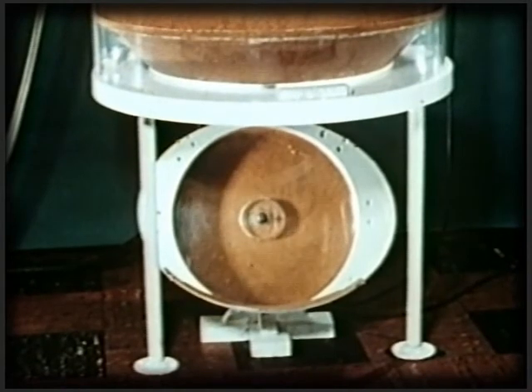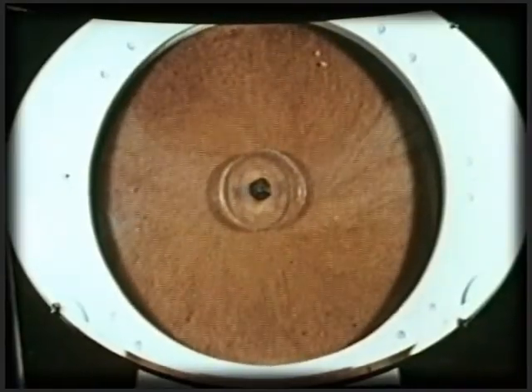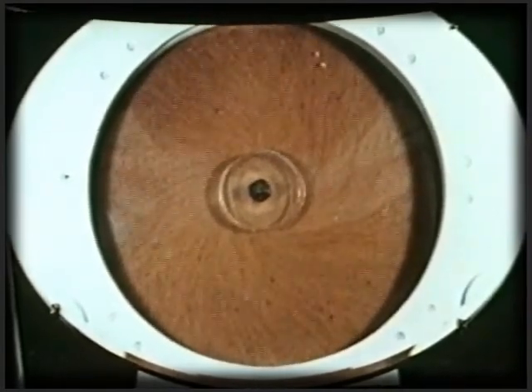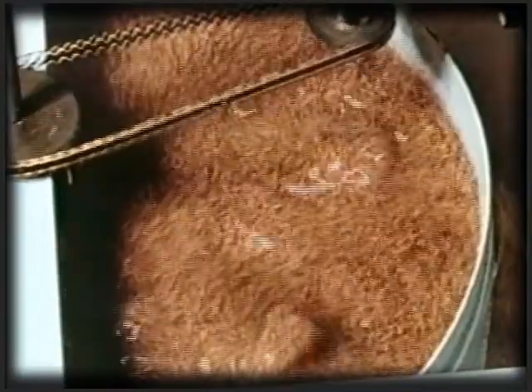A mirror below our model shows how the slurry recirculates. It's an action caused by our specially designed rotor impeller, a key to the Accelator's success. The long, flat rotor blades mix raw water and chemicals with the recirculating slurry. The impeller at the top acts as a low-lift pump to push slurry up into the secondary mixing zone.